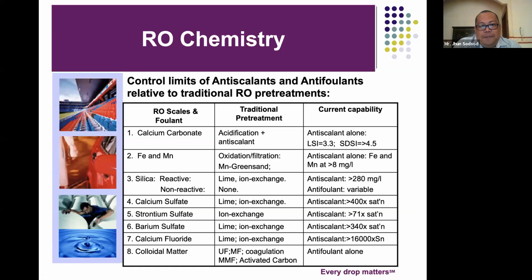A typical example is calcium carbonate, which is generally present in most of the water. The traditional treatment is to acidify it, either by adding sulfuric acid or hydrochloric acid to bring down the LSI value. In our case, our capability eliminates the dosing of acid. Our product can control calcium carbonate scale build-up, and it is applicable in a very wide range, from pH 5 to pH 10.